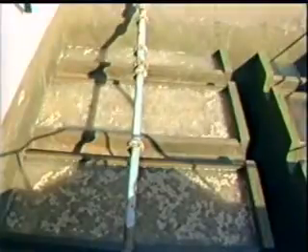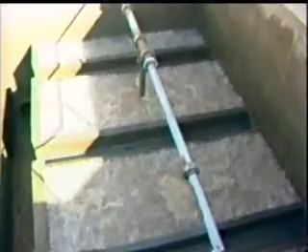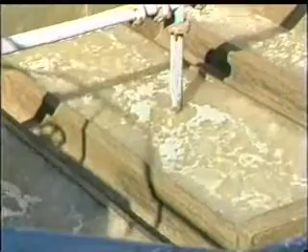Compressed air is then passed through the filter beds from bottom for about 2 to 3 minutes. This loosens the arrested impurities from filtering media that are responsible for clogging the filter beds. After this, water from the bottom of the tank is passed under pressure to wash out the impurities.